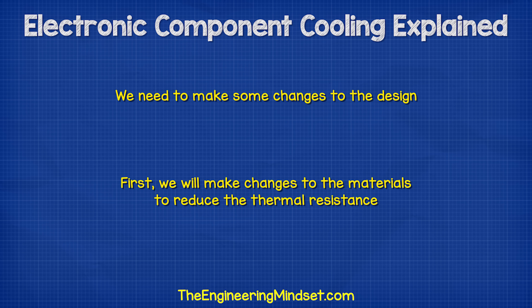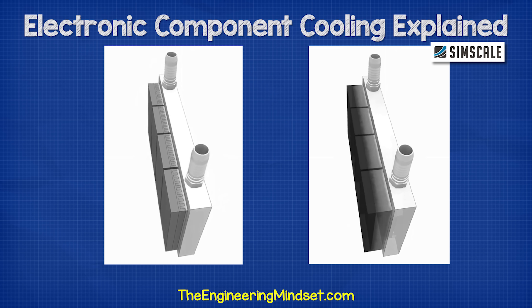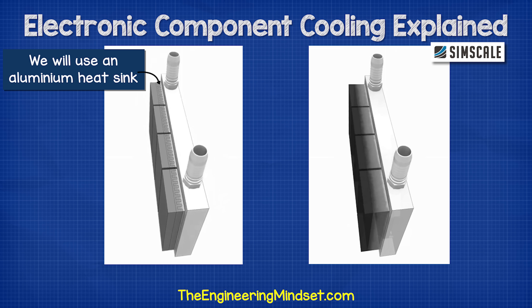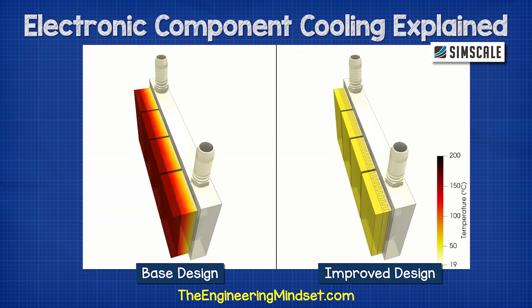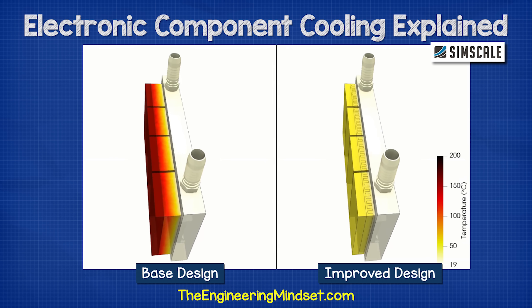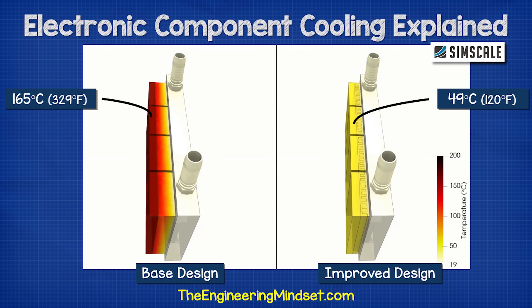The first change we will make is to the materials. We will use aluminium for the heatsink because this has a very high thermal conductivity, meaning heat can pass through it much easier. Between the IGBTs and the thermal block, we will also use a thinner layer of thermal paste, so that the IGBTs are closer to the heat transfer area, making it easier for the heat to reach the cooling liquid. As you can see, these simple changes have made a dramatic effect. Our IGBTs are now down to around 49 degrees Celsius, which is perfect because it's below our thermal limit of 90 degrees, and it also provides a good buffer before we would hit that limit.